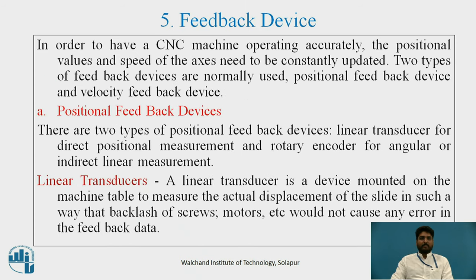Feedback devices are the fifth element. In order to have a CNC machine operating accurately, the positional values and speed of the axis need to be constantly updated. Two types of feedback devices are normally used: positional feedback devices and velocity feedback devices. There are two types of positional feedback devices: a linear transducer for direct positional measurement, and a rotary encoder for angular or indirect linear measurement. A linear transducer is mounted on the machine table to measure the actual displacement of the slides, so that backlash of the screw, motors, etc., does not cause any error in the feedback data.